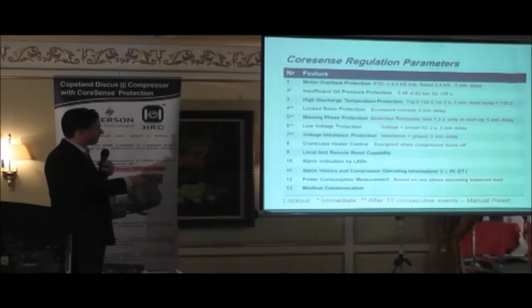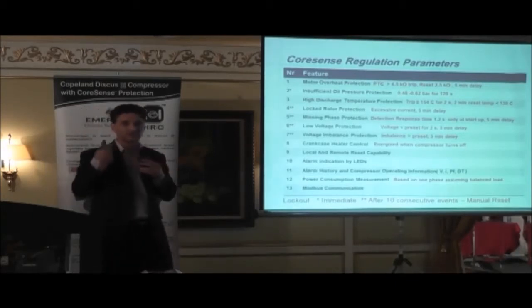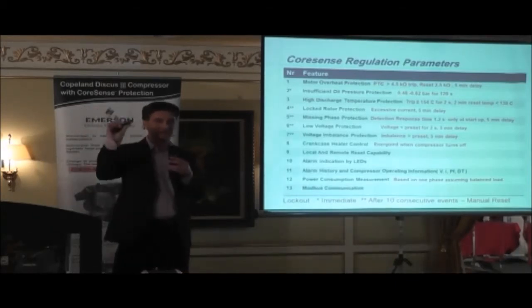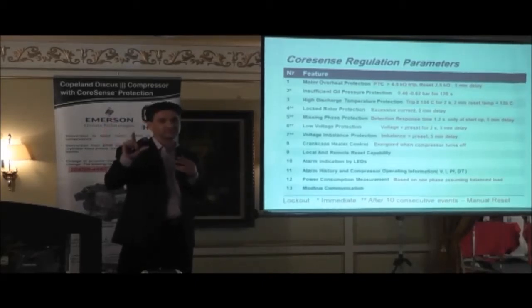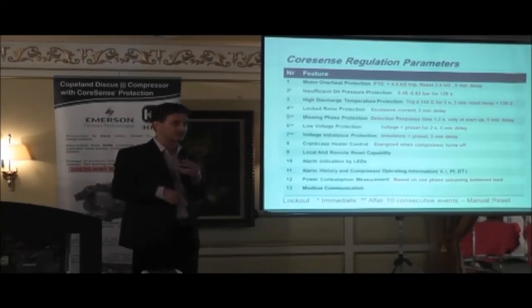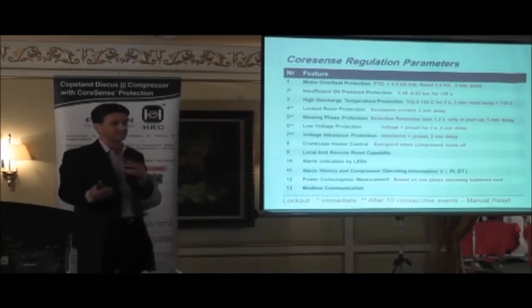Same applies for low voltage and for voltage imbalance. All of these have a 5-minute delay. Now these items here have a double asterisk. What does the double asterisk mean? It means that the compressor will try and restart 10 times. Okay? At the 10th attempt, if it fails to restart, it then goes to manual lockout. Alright? And it basically has to be reset.